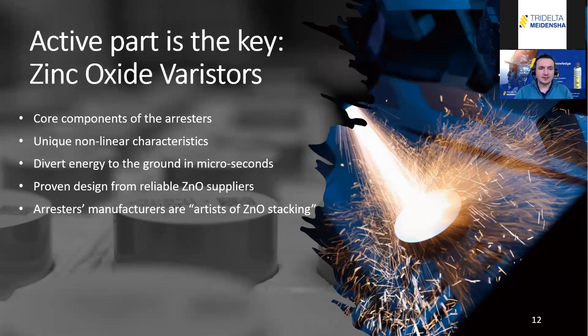And also, I like to state that arrestor manufacturers are basically artists of MOV stacking, ZnO stacking, because at the end, this is the main challenge. This is the core competence of arrestor manufacturers. We play with those blocks. We play with the diameters of the blocks in relation to the energy ratings. We play with the height, with the number of blocks, to define the voltage ratings. And of course, there are some important tests related to this because they have to handle surge duties. So they have to dissipate the energy, and so you might see different heat dissipation depending on the design.